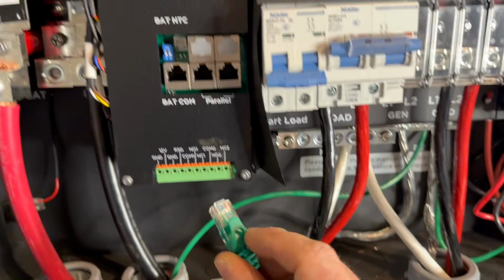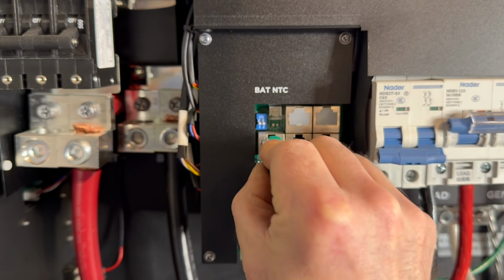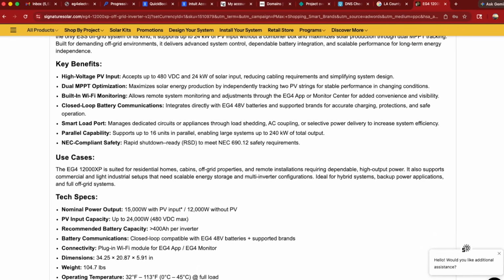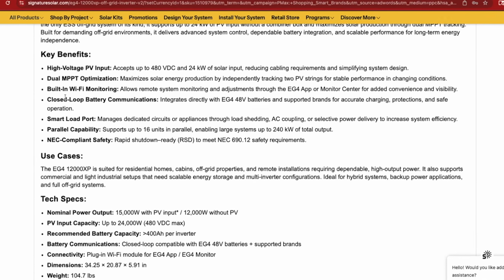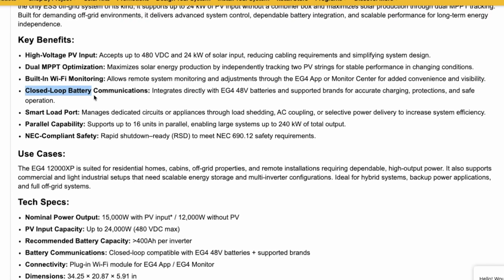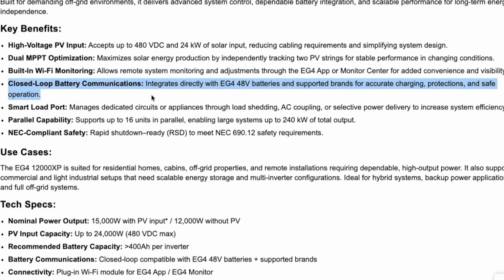It's got closed loop communications with a massive list of batteries, and what that does is have the batteries and inverter talking to each other, giving real information to make sure you're really prolonging the lifespan of that battery bank and monitoring it in a smart way. Now, open loop communication is just your inverter measuring voltage, and that's all it really knows. But closed loop communication is really what you want in a system to make sure everything functions well together and you prolong the lifespan of your batteries.